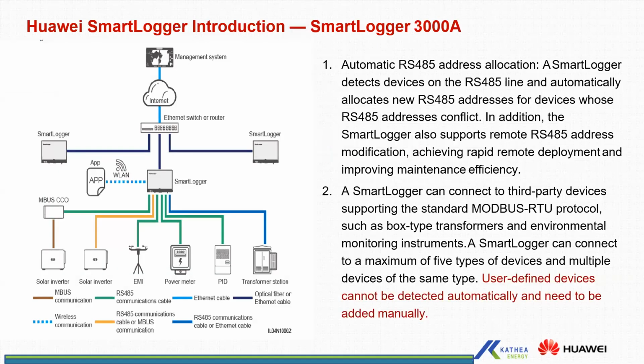So for connecting power meters, inverters, EMI, PIDs, the SmartLogger uses RS485, and then you can use TCP to connect to third-party devices. And then for transformer stations and all that, the SmartLogger also supports optical fiber connection. All right, and then for connecting to third-party devices, you can have your FTP server. You need to configure it on the SmartLogger, so the SmartLogger can push all the data to your private FTP server. You can also set the SmartLogger to send you notifications in terms of alarms and plant reports. So all those can be set on the SmartLogger, and then you can get maybe daily, monthly reports on the plant status and all that.